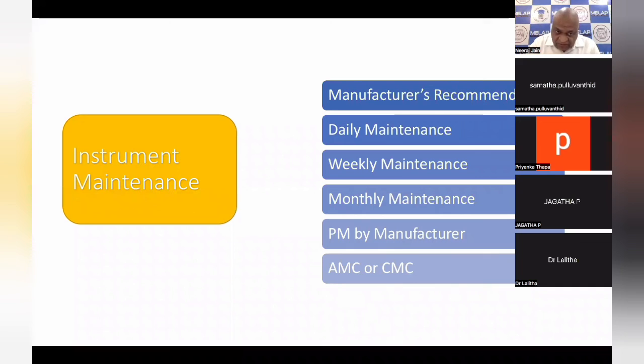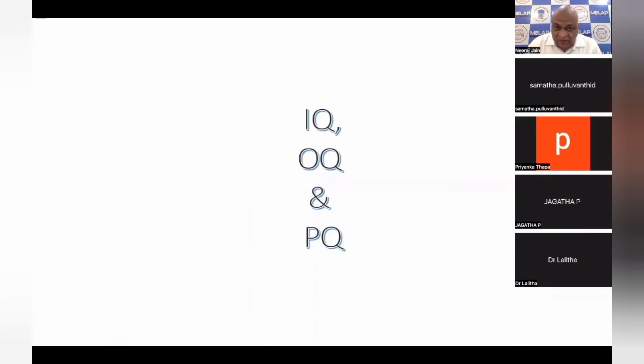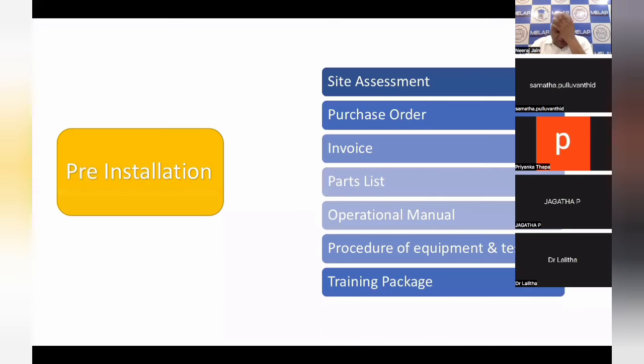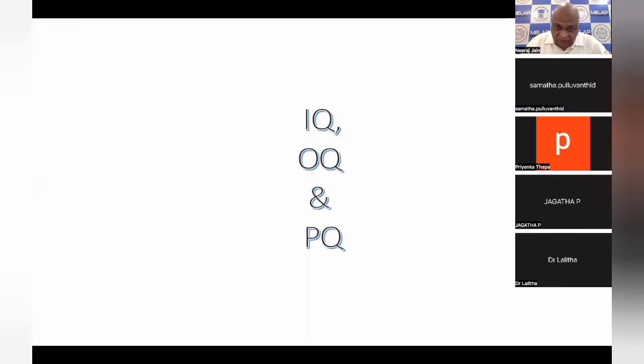With this basic concept, whatever we are doing on our machine, we will see what all records need to be maintained. And one thing is clear, whatever the standard has mentioned in 5.3.1.7, all those shall be there in your equipment file, and you can maintain it like this: IQ, OQ, and PQ. Installation qualification, operational qualification, and performance qualification.